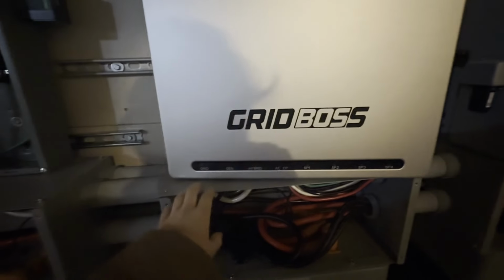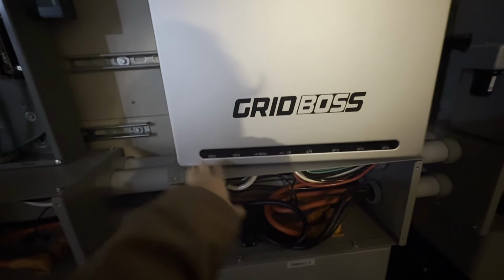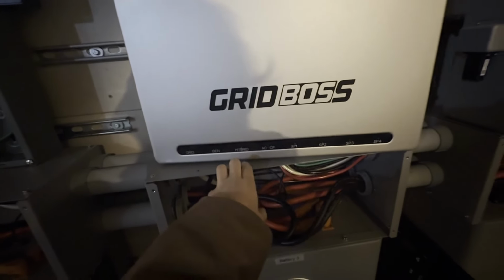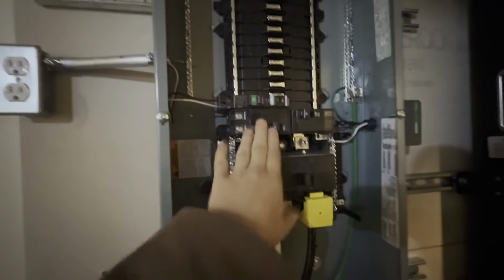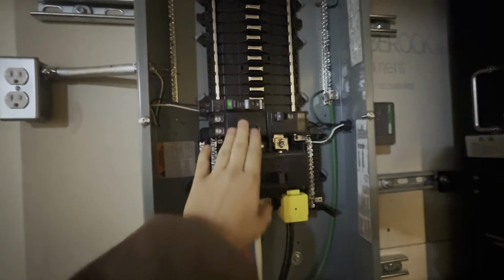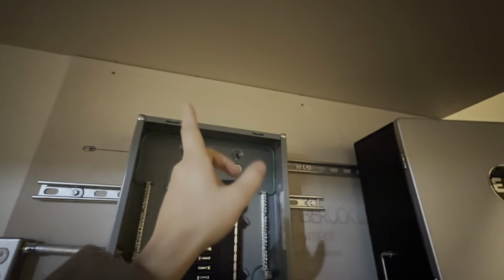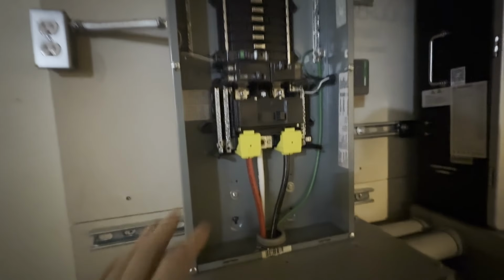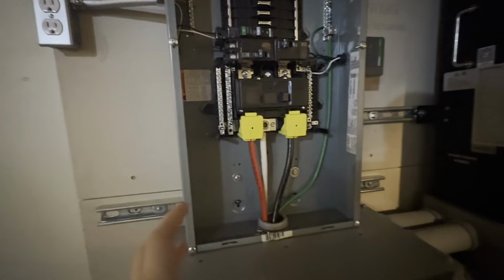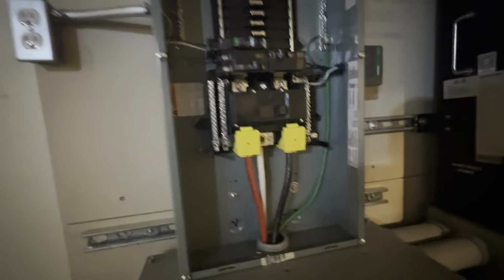Let's see. So yeah, this is what the grid boss looks like on the outside. It's got LEDs here to tell you what's going on. So you can see generators running, grid's up, hybrid inverters are on, etc. This is the house main panel. Now this breaker here, right now it's a 70. It's actually going to get swapped out for a 100 amp because I'm going to be putting in some conduit, the 1.25" conduit. And it's going to run all the way outside and around the house to the old main panel. And so the old main panel will be a sub panel of this one once I swap over the service.